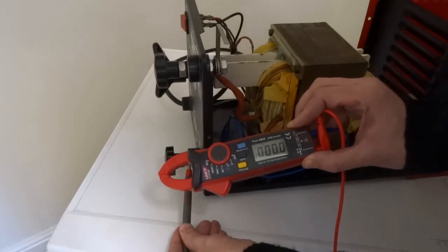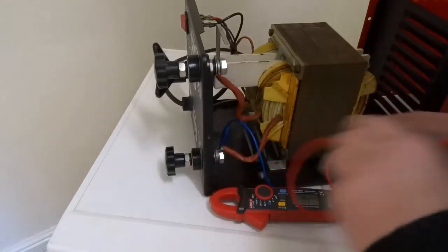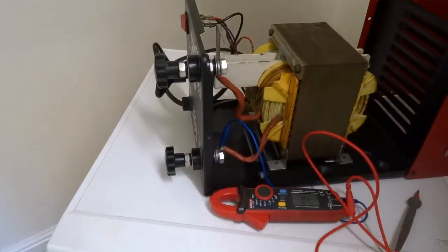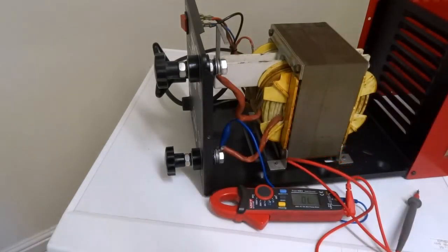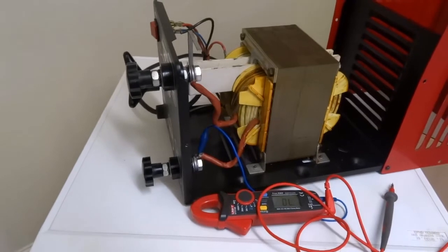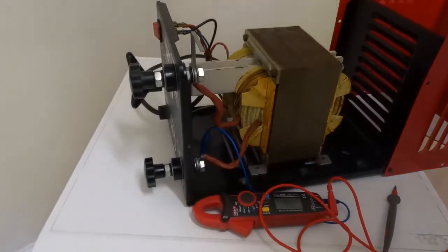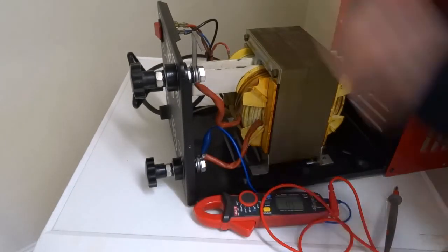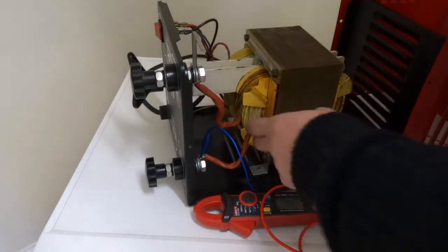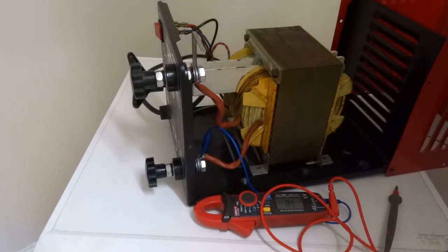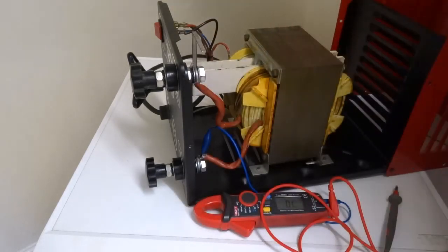So that's it. I know that all connections are fine, I know both transformer windings are fine, the switch is fine, the cable's good, so this is a good working arc welder. That's about it, nothing else really to mention - all the switch, cable, thermal cutout, and the primary and secondary transformer windings. Everything else is cheap; if that's gone, you're probably going to have to buy a new welder.